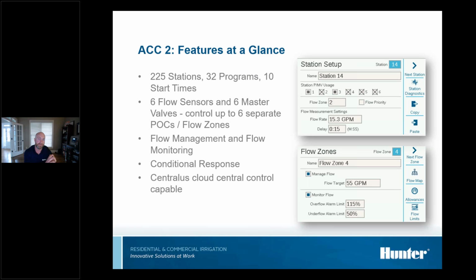It has some really powerful flow features, flow management, which basically means it will learn the flow of each individual station. And then if you need to set a flow target, so you see down in this bottom screen here, if you know you have a 2-inch water main and you want to keep it within IA specs for velocity, which is 5 feet per second, you know it's going to need to be 55 gallons a minute. So you can set the max flow that will never exceed 55 gallons a minute. Then it will go out and find zones to make up 55 gallons a minute. When one zone is done irrigating, it'll find something else that's close to make that 55 up. So it will run your automatic irrigation program as close as possible to 55 gallons per minute all night long.